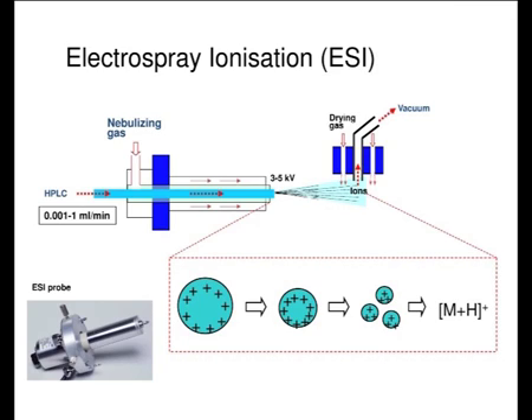Then, due to the high temperature, the solvent starts evaporating. There are two forces acting on the solvent droplet. One is the Coulombic force of repulsion between same charges. The second is surface tension. The surface tension tries to keep all the ions together, but the Coulombic force of repulsion tries to push them far from each other. Once the Coulombic force of repulsion overcomes the surface tension, that is known as the Rayleigh limit, the ions get separated. They come out, and finally enter the mass spectrometer through the desolvation line. This is the phenomenon which occurs in electrospray ionization. Generally, electrospray ionization is used for polar compounds, and for protein analysis, in most cases, ESI is the only technique used for ionization.